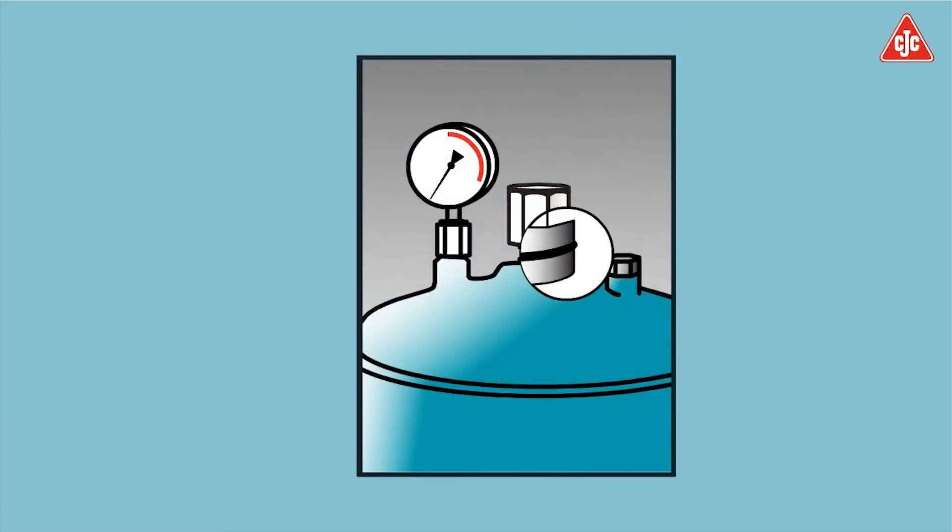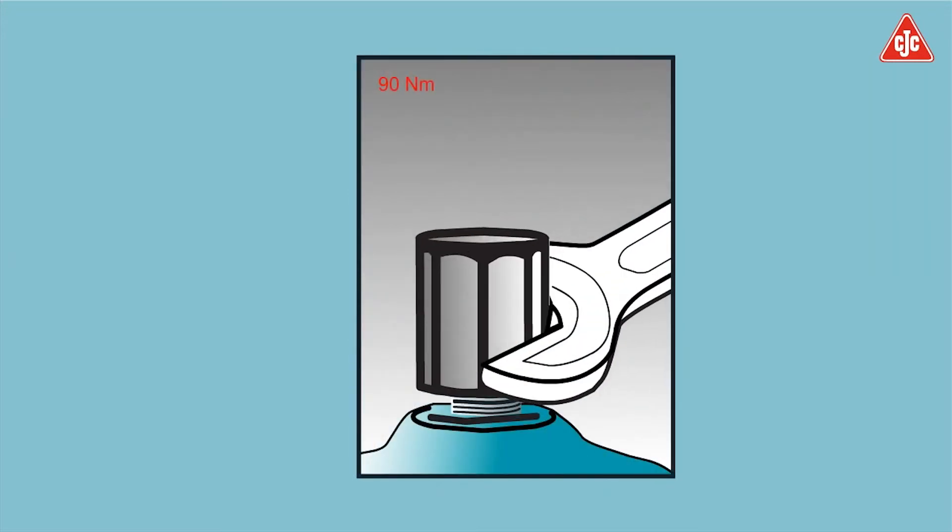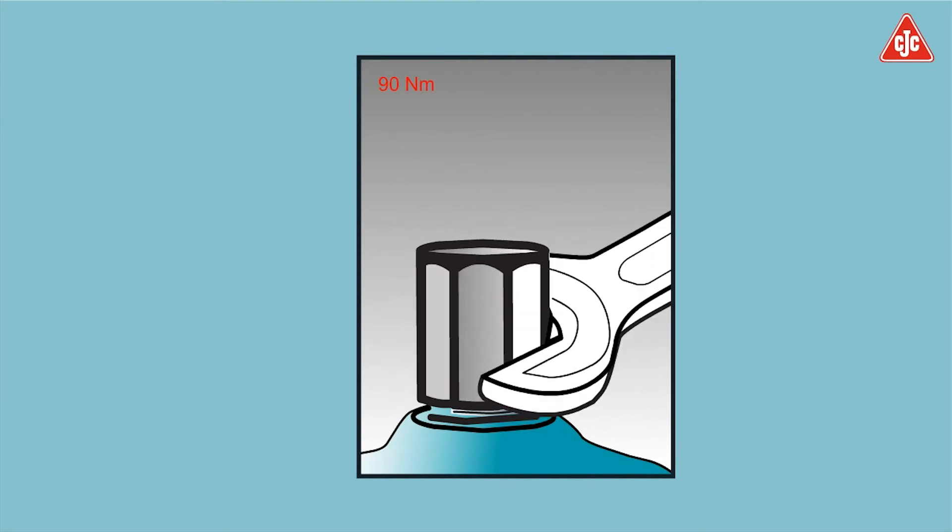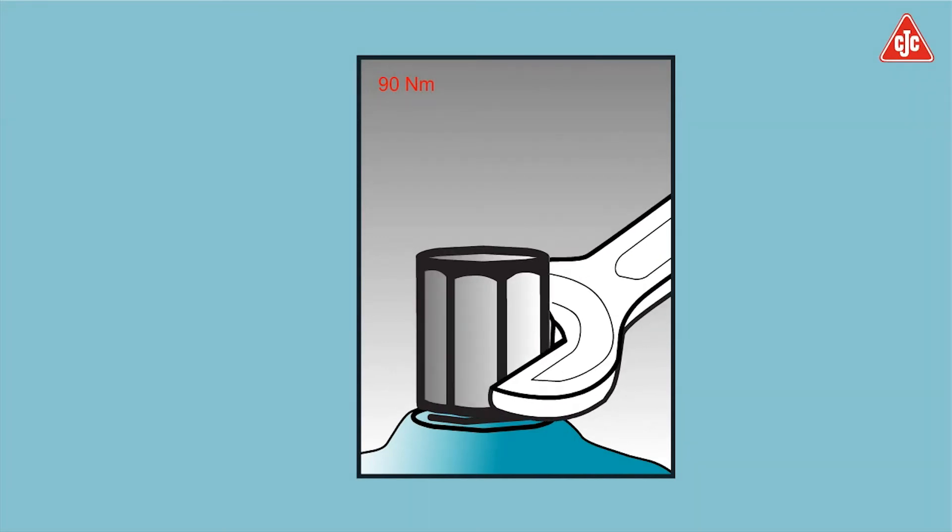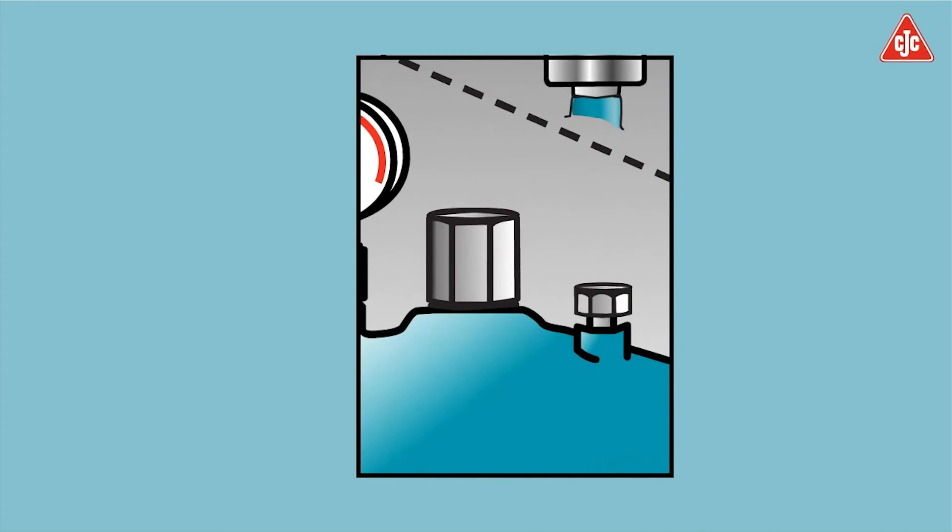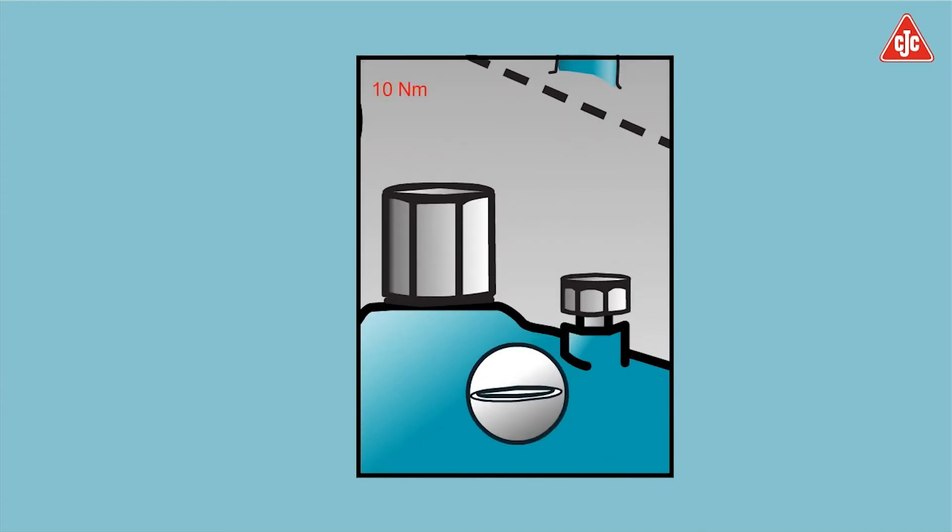Replace O-ring for top nut. Tighten top nut with torque of 90 Nm. If equipped with an automatic air vent, no action is taken. If equipped with an air vent screw, replace the O-ring for air vent screw and tighten with torque of 10 Nm.